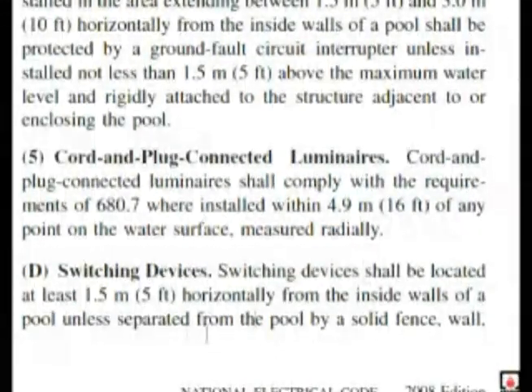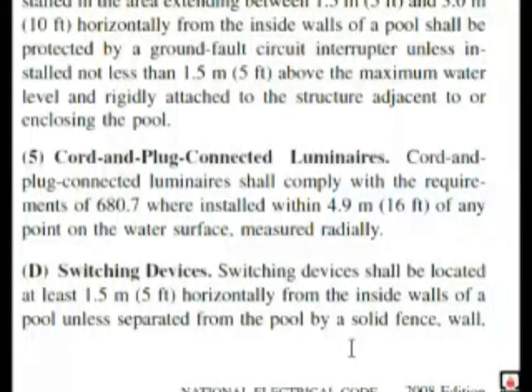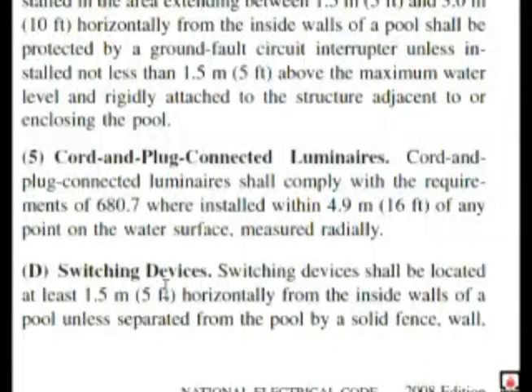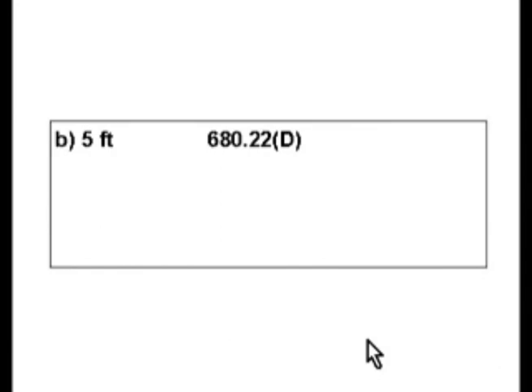Here we are at section 680.22d and it says switching devices shall be located at least 1.5 meters or 5 feet horizontally from the inside walls of a pool unless separated. This is word for word. It seems pretty obvious — you would guess 5 feet — but we don't want to guess on our exam. We want to be able to find every single answer if we don't know it off the top of our head. So the answer is 5 feet, which is B.